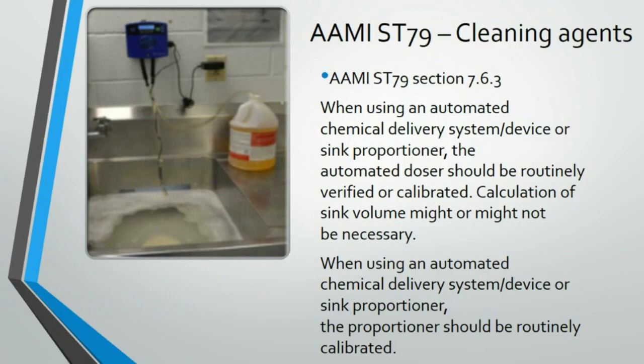ST79 also talks about cleaning agents in 7.6.3 when using an automated chemical delivery system or device or sink proportioner. The automated doser should be routinely verified and calibrated. Again, this chemistry and water work together, and if we're not making sure that that automatic doser, where we're just pushing the button, is actually giving us what it says it should when it should, we can have problems.